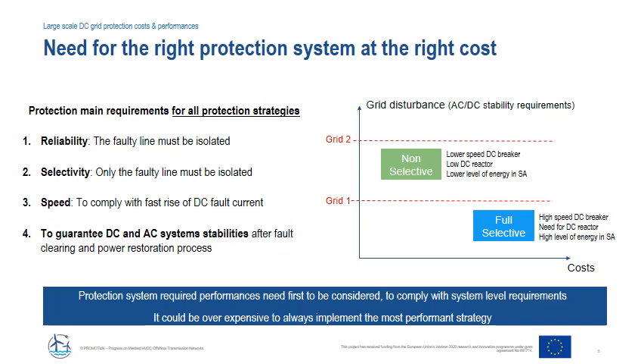In the end, it can be said that protection system performance needs first to be considered in order to comply with the system-level requirements, but that it could be overly expensive to always implement the most performant strategy. Therefore, we need to assess the performance and the cost of the protection system in order to be able to select the strategy with the right performance at the right cost. A dedicated methodology for this technical and economic assessment of protection systems for DC grids was developed for such a purpose.